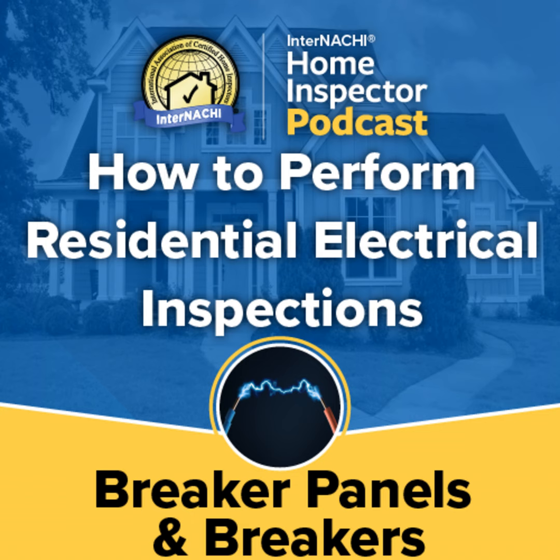However, if a GFCI breaker is installed at the panel board, it will provide protection to all receptacles downstream from that breaker in that branch circuit. AFCI and GFCI breakers have integral trip and reset buttons to help ensure that they are working properly. The home inspector should trip the breaker using the test button and ensure that the circuit has indeed been switched off.